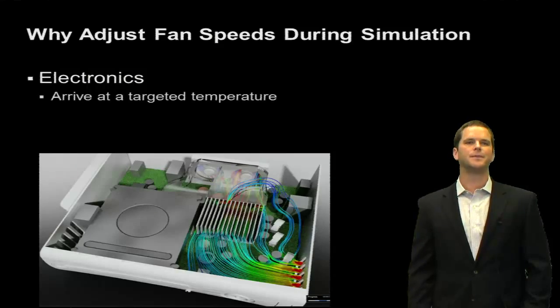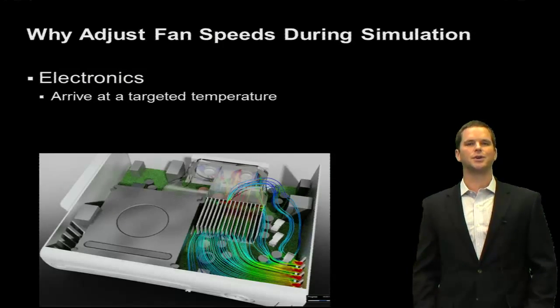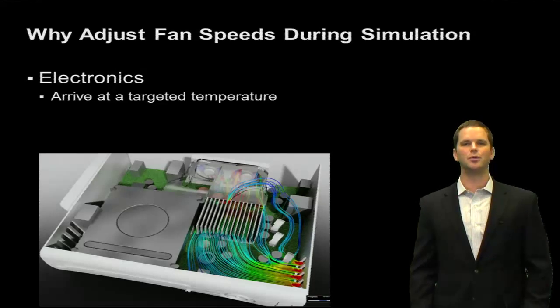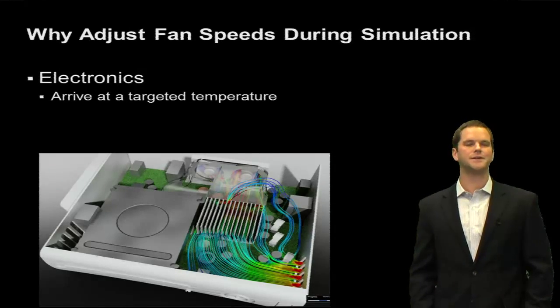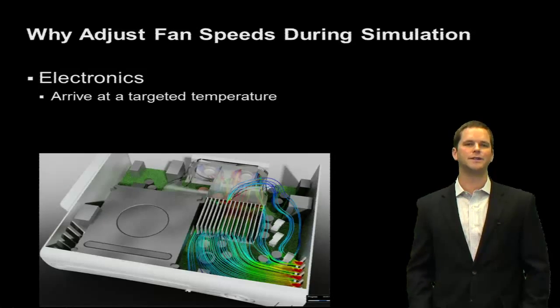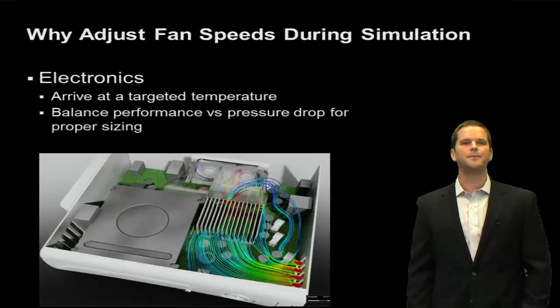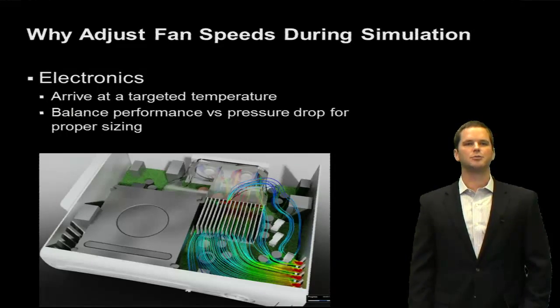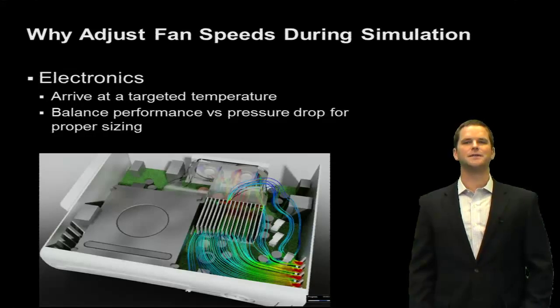But why would we want to adjust that? We want to arrive at a targeted temperature for our chips, components, LEDs, and circuit boards. We have data sheets that tell us exactly what their maximum temperatures are. So we want to apply a safety factor and come in below those, but not over-size the fan as well. We want to balance performance versus pressure drop so that we can properly size the fan.